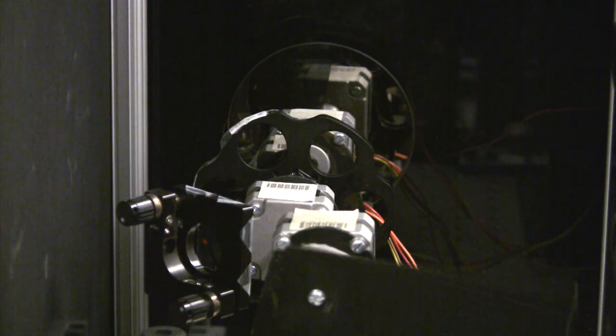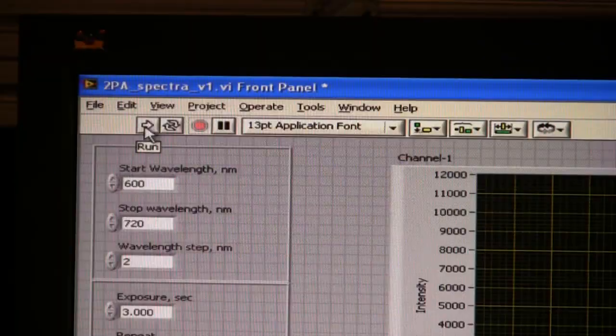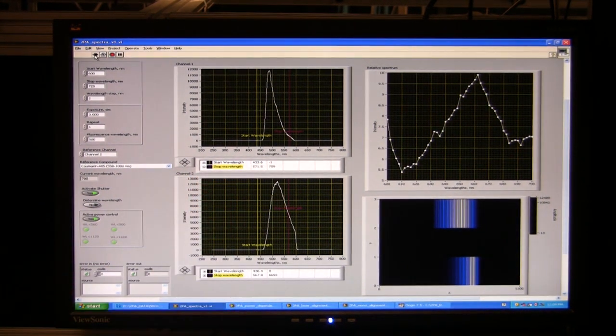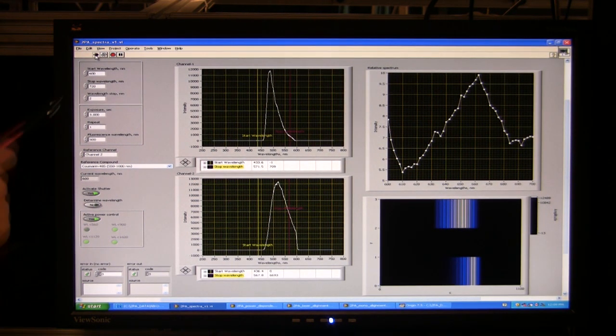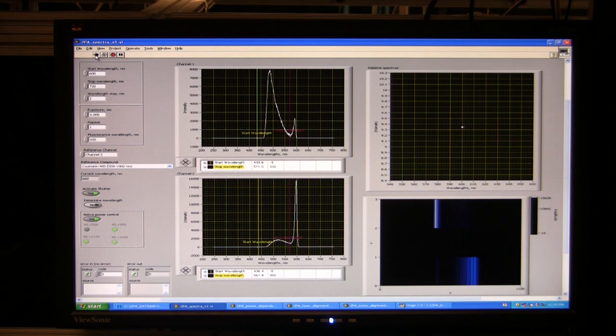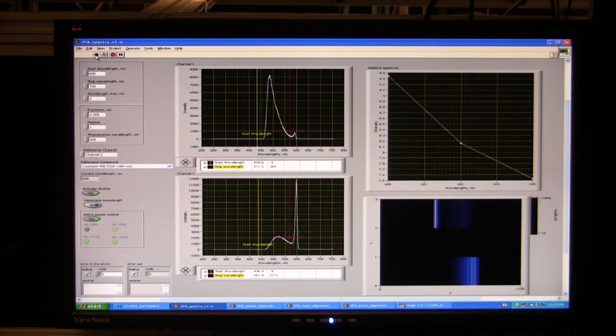When the scan is done the shutter closes, and eventually the filter wheel will go back to its original position. Now we are going to run this, so first it opens the shutter, and then it goes to specific wavelengths of monochrometer to have those wavelengths. And then it starts doing acquisitions for each wavelength starting from 600, and then stepping further away with 2 nanometer steps towards 720 nanometers.